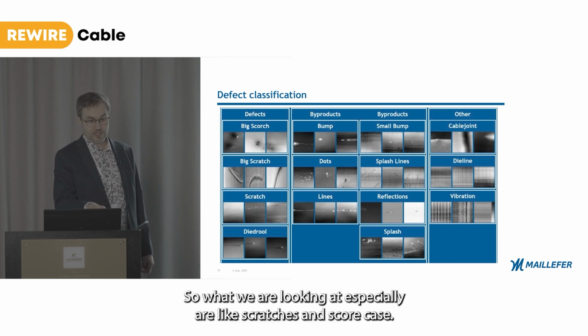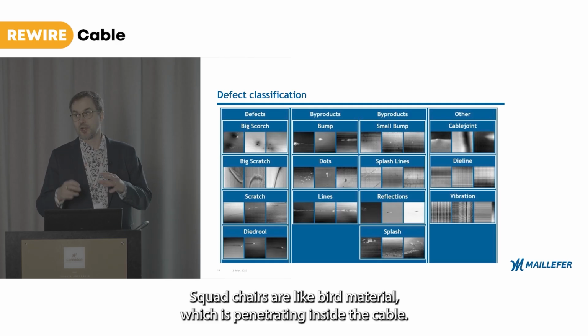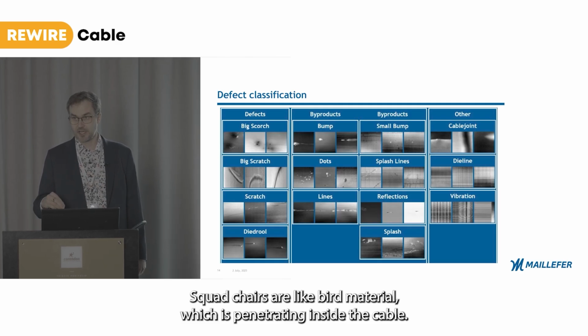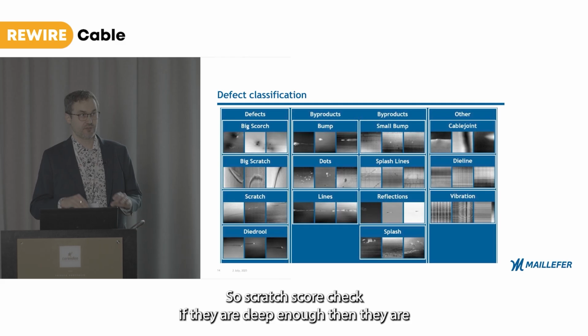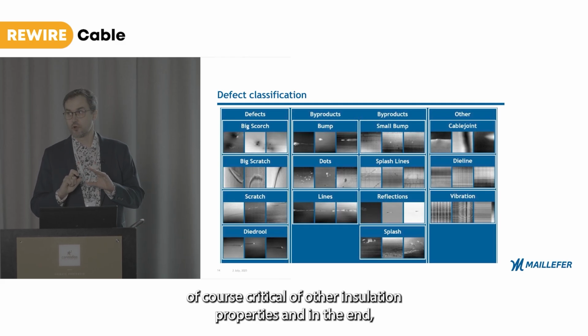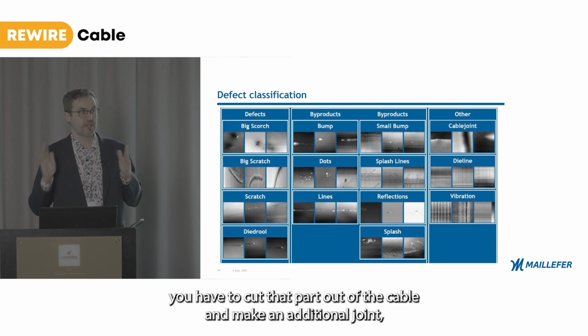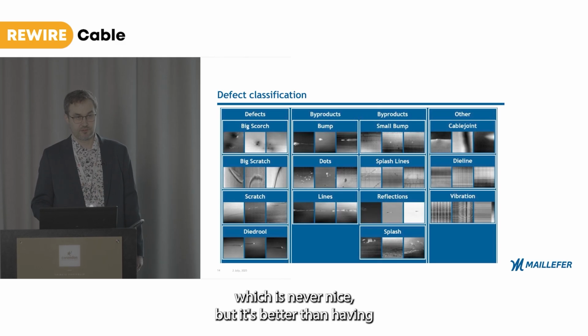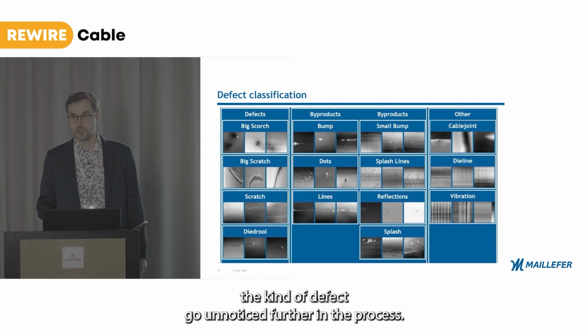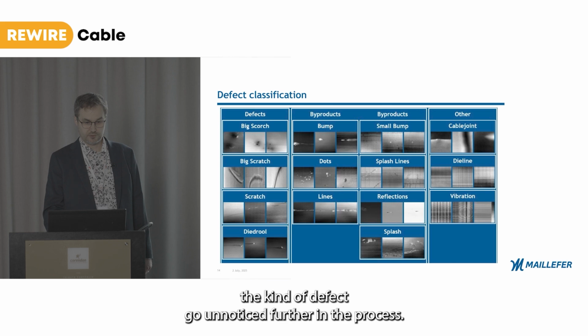What we are looking for especially are scratches and scorches. Scorches are burned material penetrating inside the cable. So scratches and scorches, if deep enough, are critical for the insulation properties, and in the end you have to cut that part out of the cable and make an additional joint, which is never nice, but it's better than having that kind of defect go unnoticed further in the process.